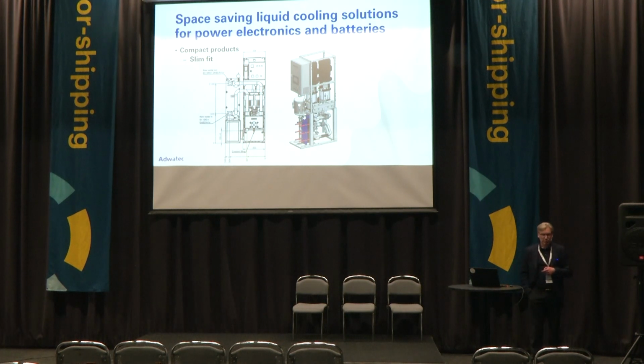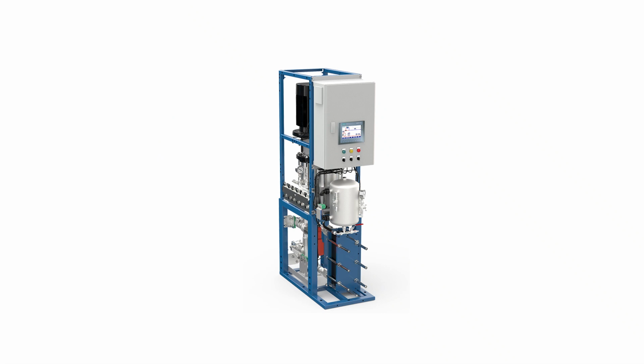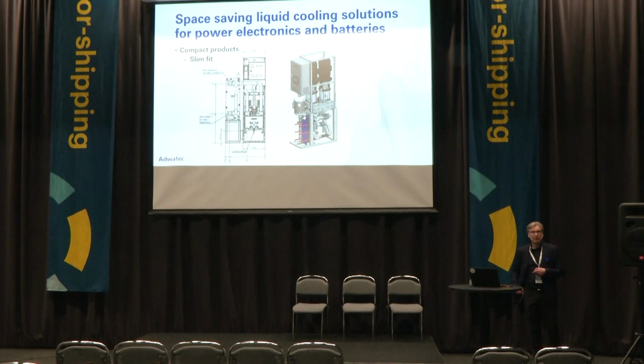Last year, we came out with a new idea: to install the pumps one behind each other. And for this kind of massive cooling application, we managed to reduce the size of the device to roughly the width of the pump, with the heat exchanger nicely installed in the same section down here. The secret to doing this successfully is again the same thing: the manifolds. We have very slim aluminium manifolds on the side of these pumps, which eliminates the need for pipes to make the required connections to the system. This is the narrowest or slimmest solution out in the marketplace right now for this kind of application.